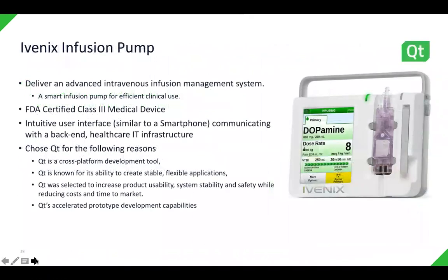And finally, we are in infusion pumps. One of them that we are in is an Ivenix infusion pump. Fully touchscreen, class 3 device, FDA certified. They were looking for an intuitive user interface similar to a smartphone experience, right? Because the benchmark for these touchscreen user interfaces exists in our pockets or our purses. But it has to be safe, reliable, and effective.